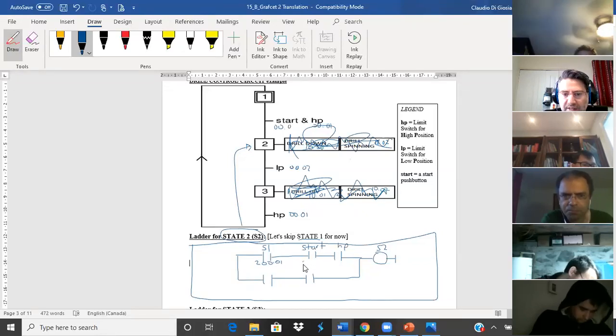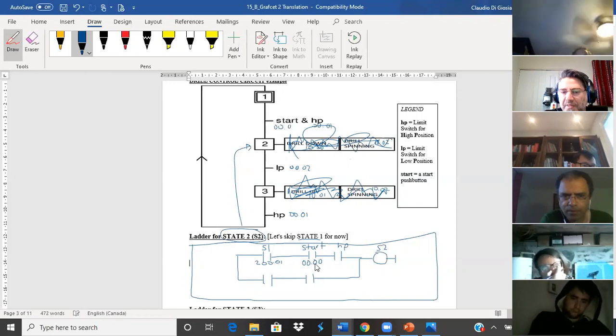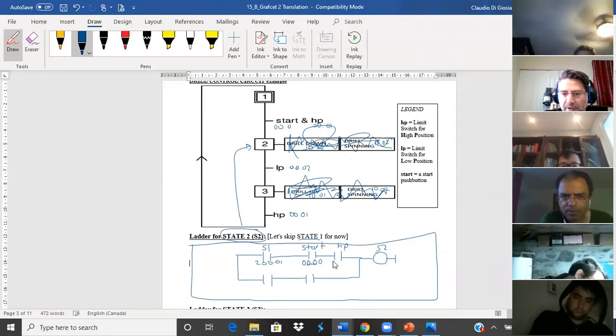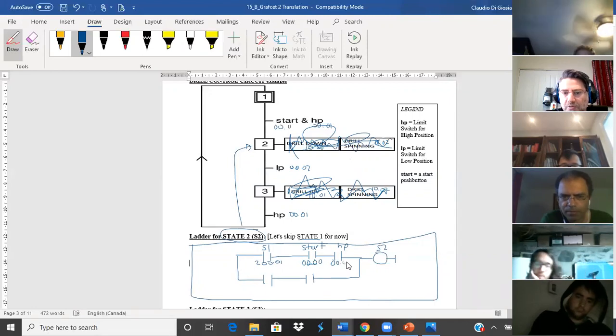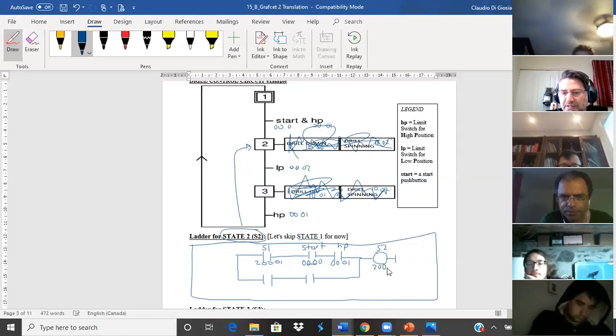Don't use zero-zero; we're going to be using 200.00 for something else. Start is 000.00. Just have the word there for now — eventually when we wire it up, this bit will be whatever address the start push button is wired to. The high position is 000.01. Work bit 200.02 — it's state two, so I'm going to use 200.02.